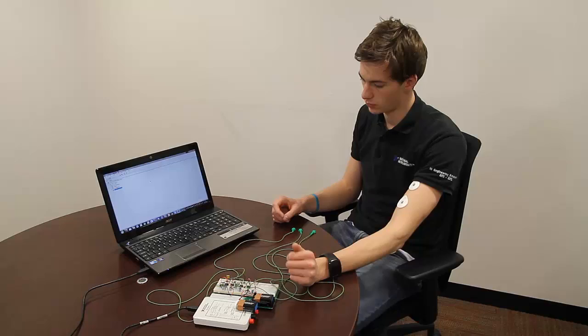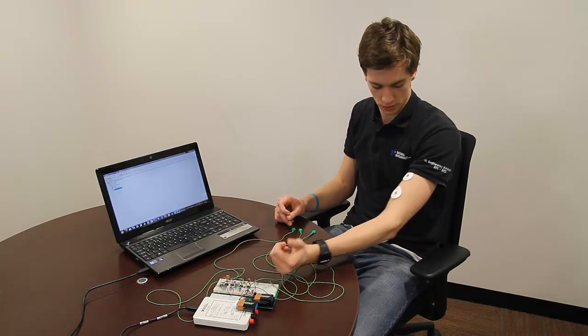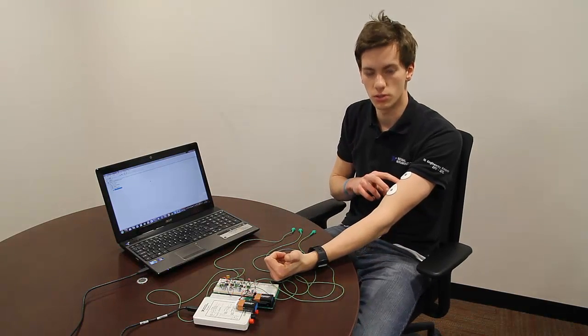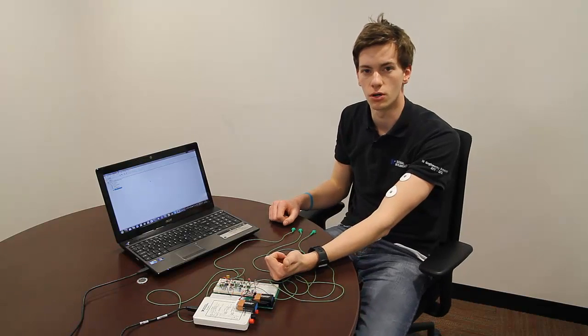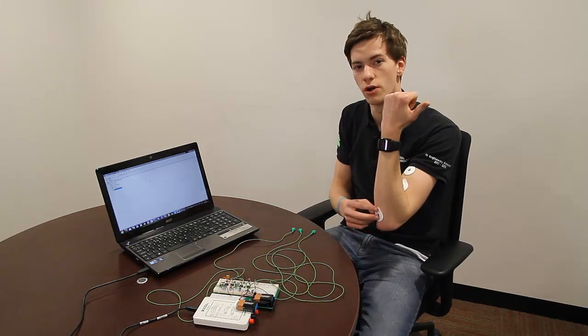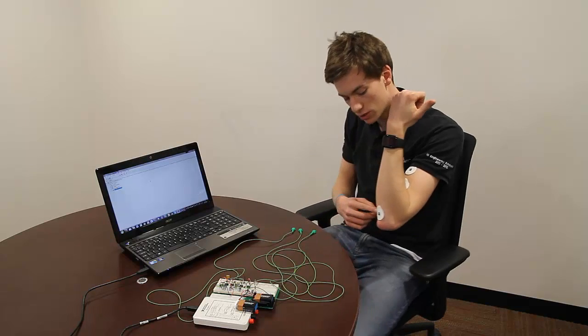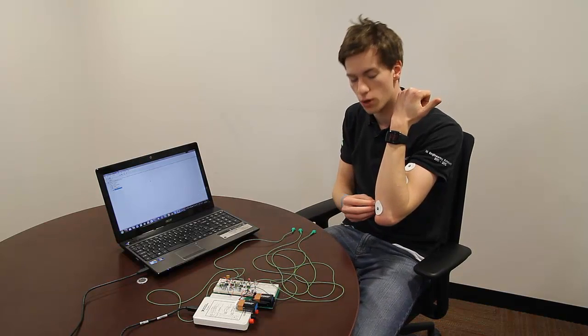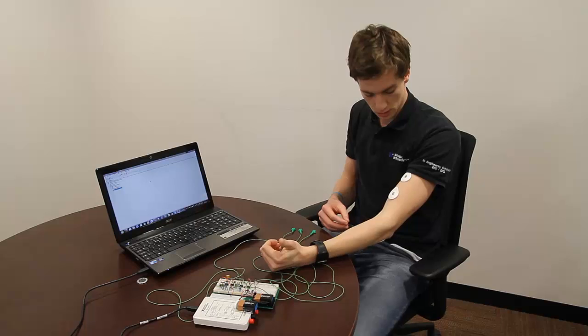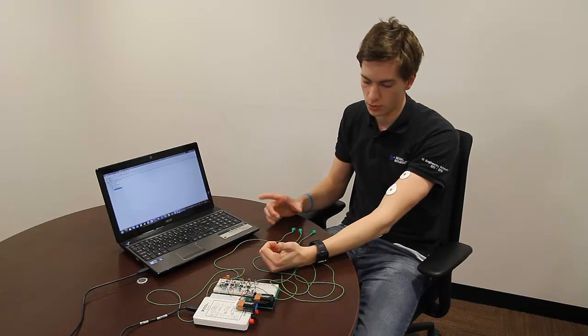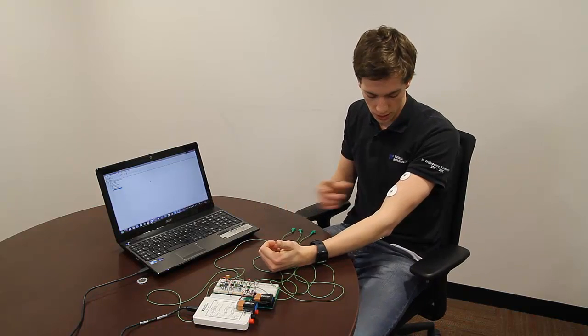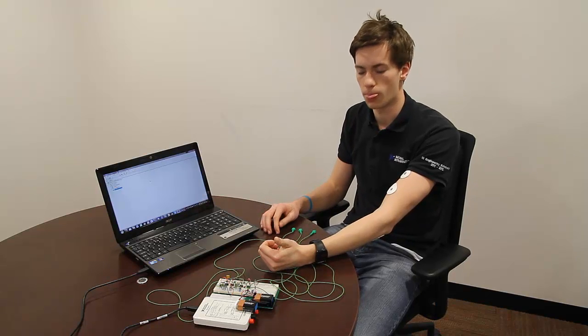The way in which the measurement works is that we're taking a differential measurement, so we need two electrodes on the muscle group and then one as a reference. The reference electrode needs to be somewhere where there's a lot of bone near the surface of the skin. The other two need to be placed on top of the muscle group, but in an area where movement artifact won't be a problem.